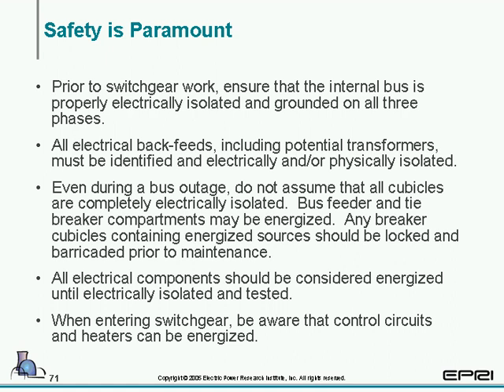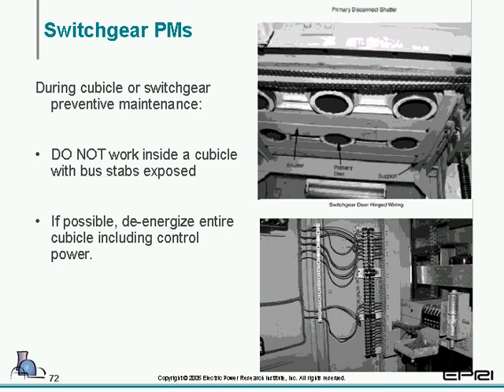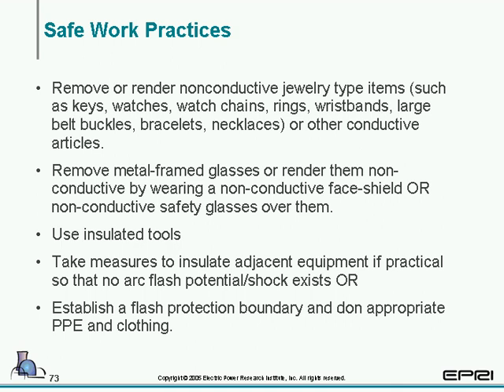When entering switchgear, be aware that control circuits and heaters can be energized. This is typically, maybe during a PM. And this is slightly redundant. Gene's already mentioned this several times, but of course, during cubicle or switchgear preventive maintenance, do not work inside a cubicle with bus stabs exposed. Obviously, if the bus is live, during a bus outage, you may be working in there, but if you have a live bus, and for whatever reason the bus stabs are exposed, you should reconsider that. If possible, de-energize the entire cubicle, including control power.